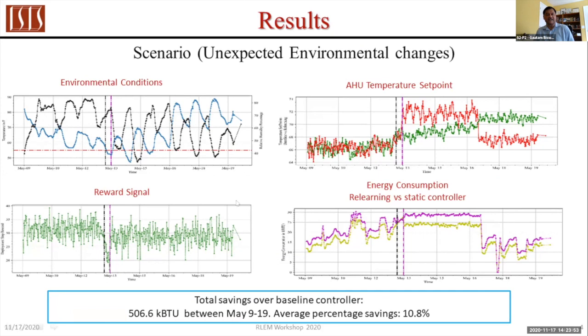As a result, we relearn the controller, and the new controller sets the discharge temperatures slightly higher to compensate for the cold conditions outside. This gives significant energy savings compared with staying with the original controller. Interestingly, after a few days the environmental conditions return to normal, and the controller again adjusts.